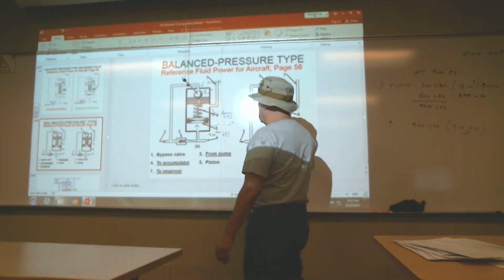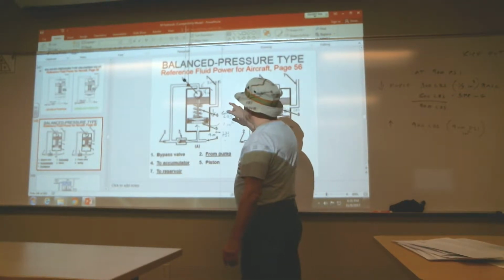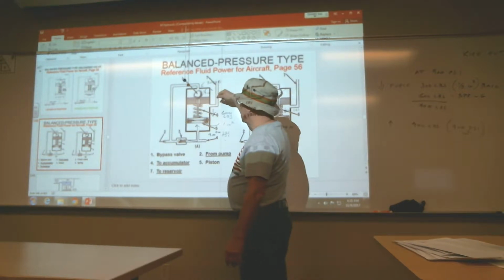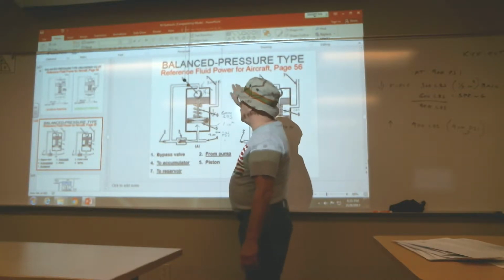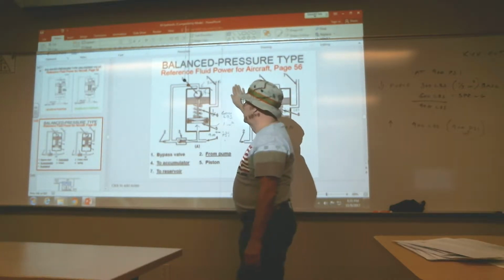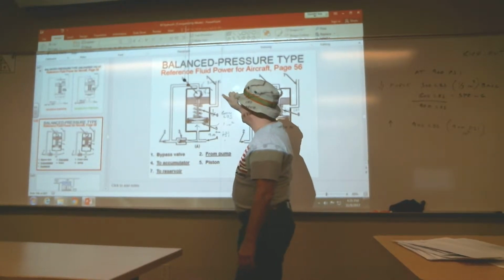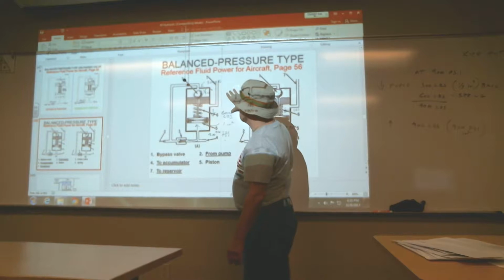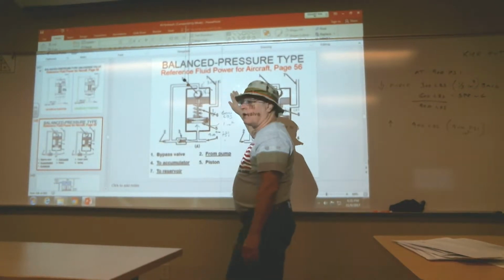So okay, you got that. But what's pushing down? In a couple of cases you've got the spring, 600 pound force pushing down. And if the surface area of the ball that's also aiding in holding the relief valve seated is 1/3 of a square inch, 600 plus 300 is a total of 900.